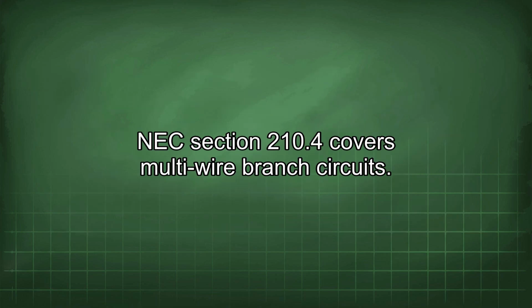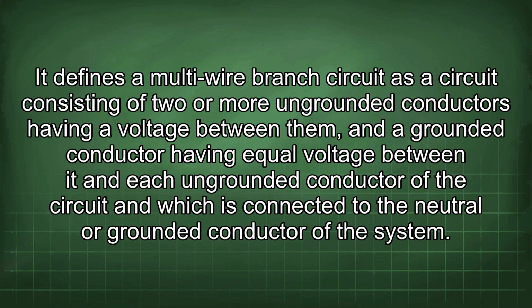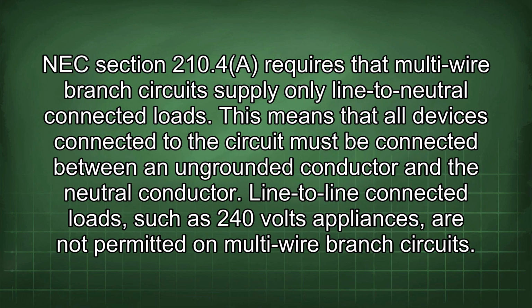NEC Section 210.4 covers multi-wire branch circuits. It defines a multi-wire branch circuit as a circuit consisting of two or more ungrounded conductors having a voltage between them, and a grounded conductor having equal voltage between it and each ungrounded conductor of the circuit, and which is connected to the neutral or grounded conductor of the system. NEC Section 210.4 requires the multi-wire branch circuit to supply only line-to-neutral connected loads. This means that all devices connected to the circuit must be connected between an ungrounded conductor and the neutral conductor. Line-to-line connected loads, such as 240 volt appliances, are not permitted on multi-wire branch circuits.